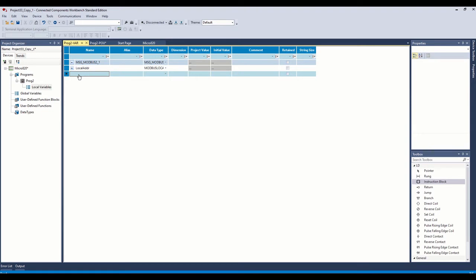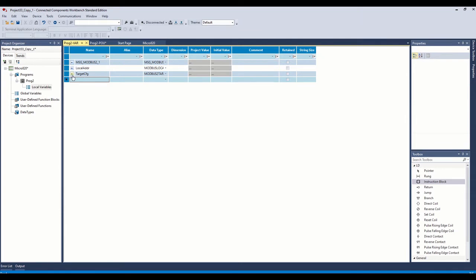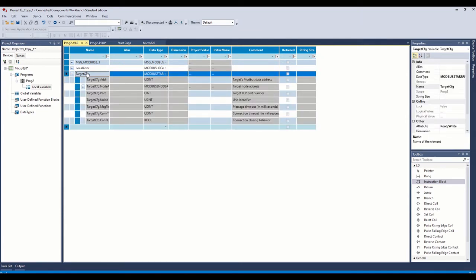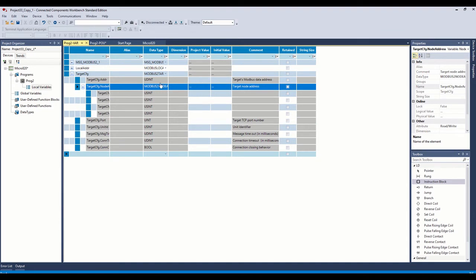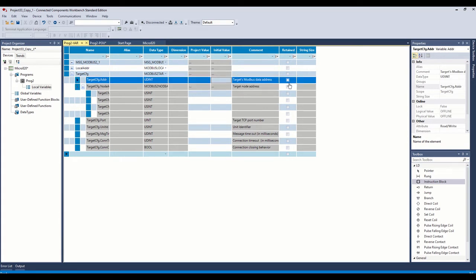The next one we're going to do is our target config. So this is the Modbus 2 target parameters. And this one gives the message instruction all the information it needs to know about the target location. First of all, we need the Modbus data address. So we're going to start reading at the first holding register at our target, which is a Micro 1400. We're going to read the first holding register, so we're going to put a one in there.